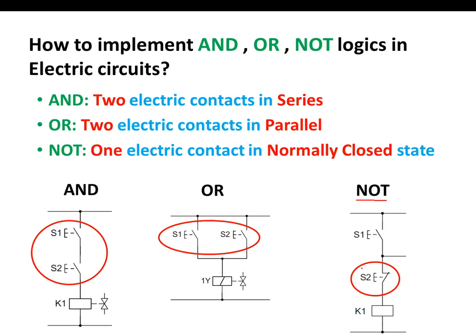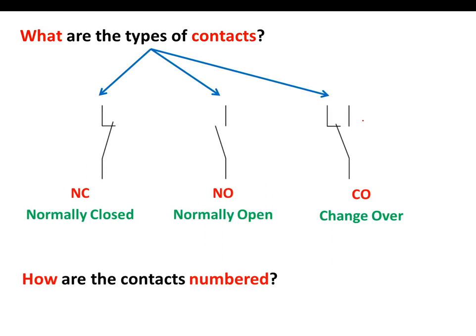What are the types of contacts? We have three types: normally closed, normally open, and a changeover which combines both. So we have two in one — normally closed plus normally open. These contacts must have numbers, and these numbers are fixed: 1-2 for normally closed, 3-4 for normally open, and 11-12-14 for the changeover contact.